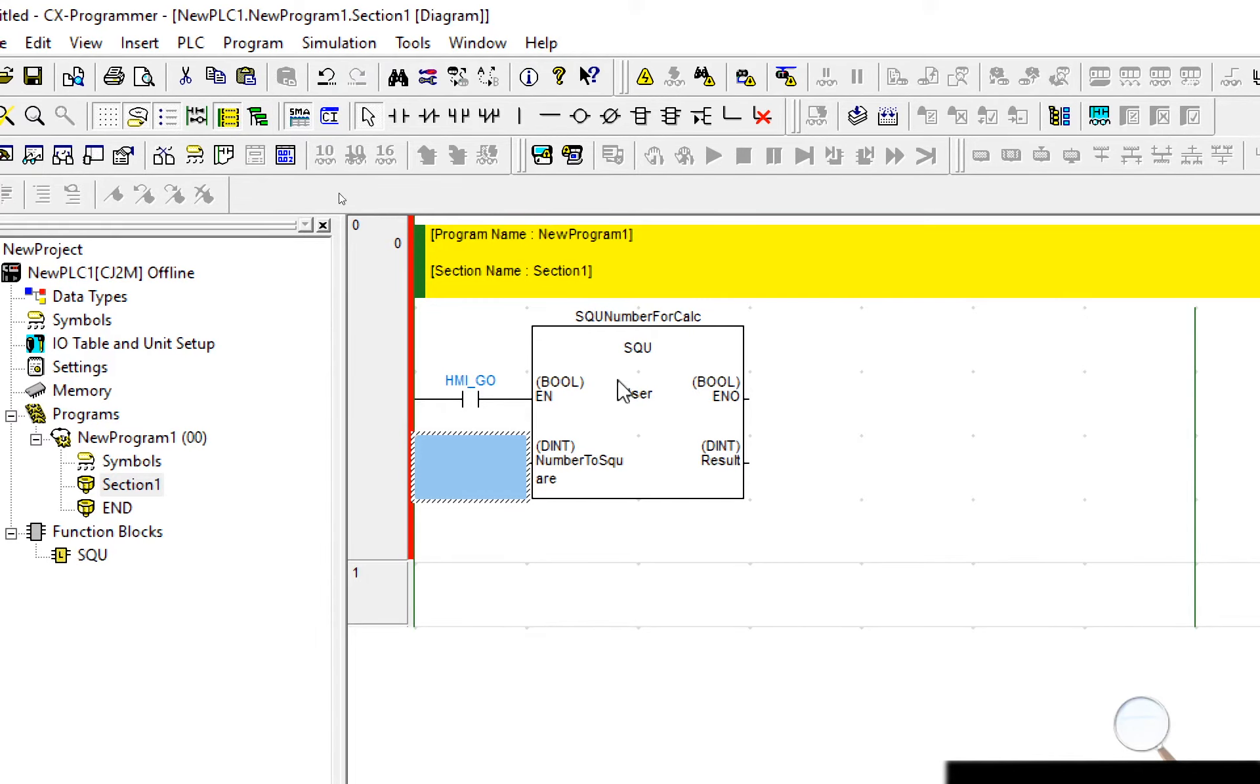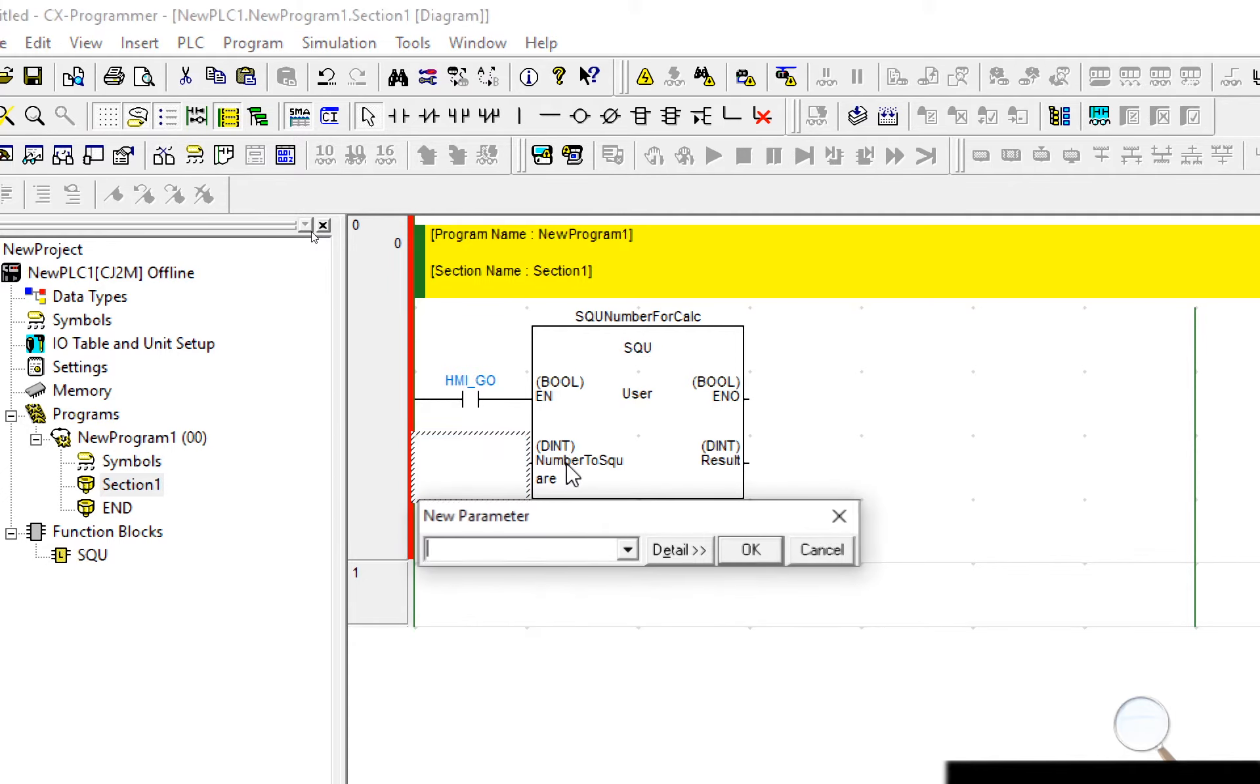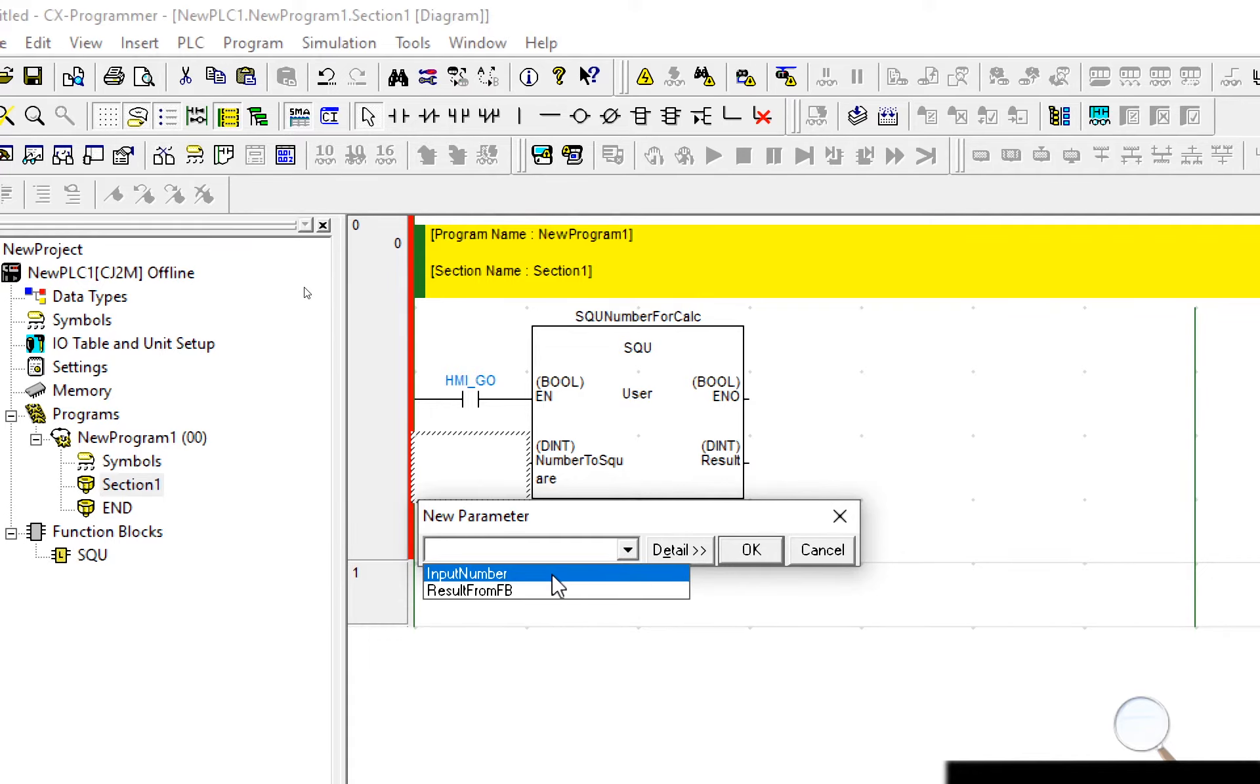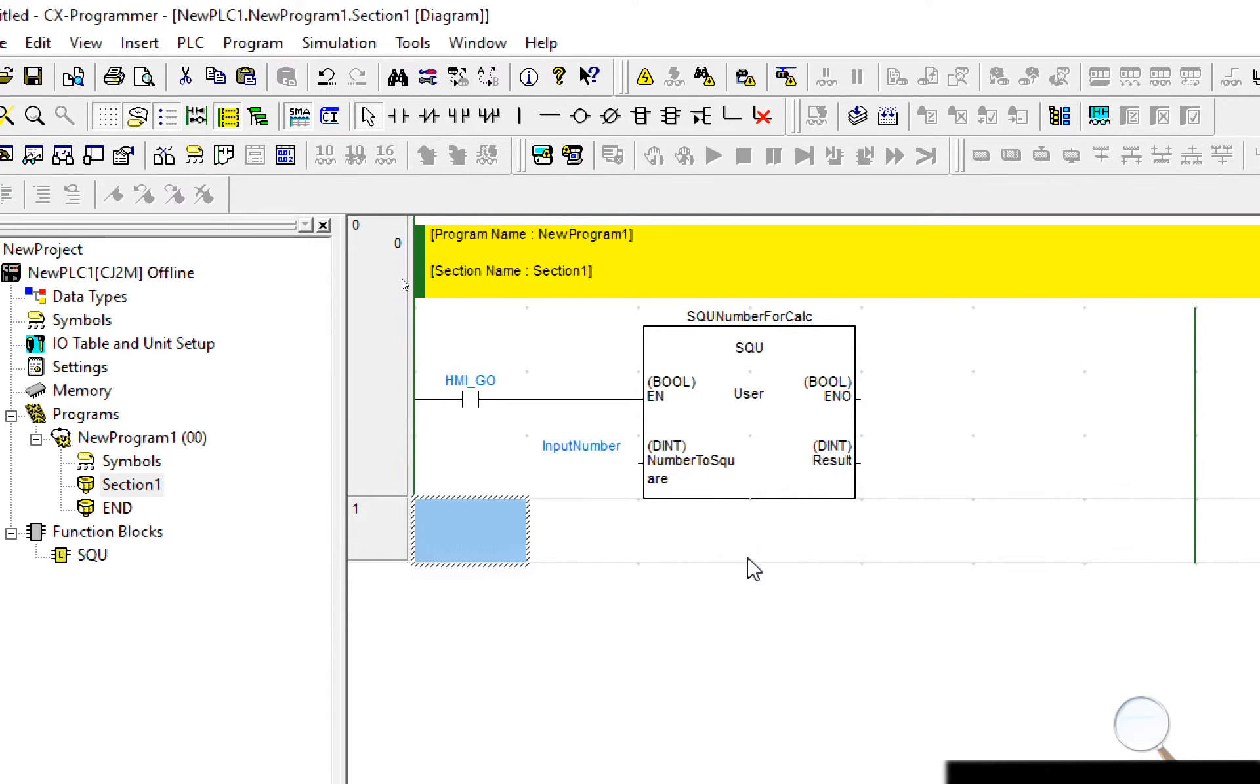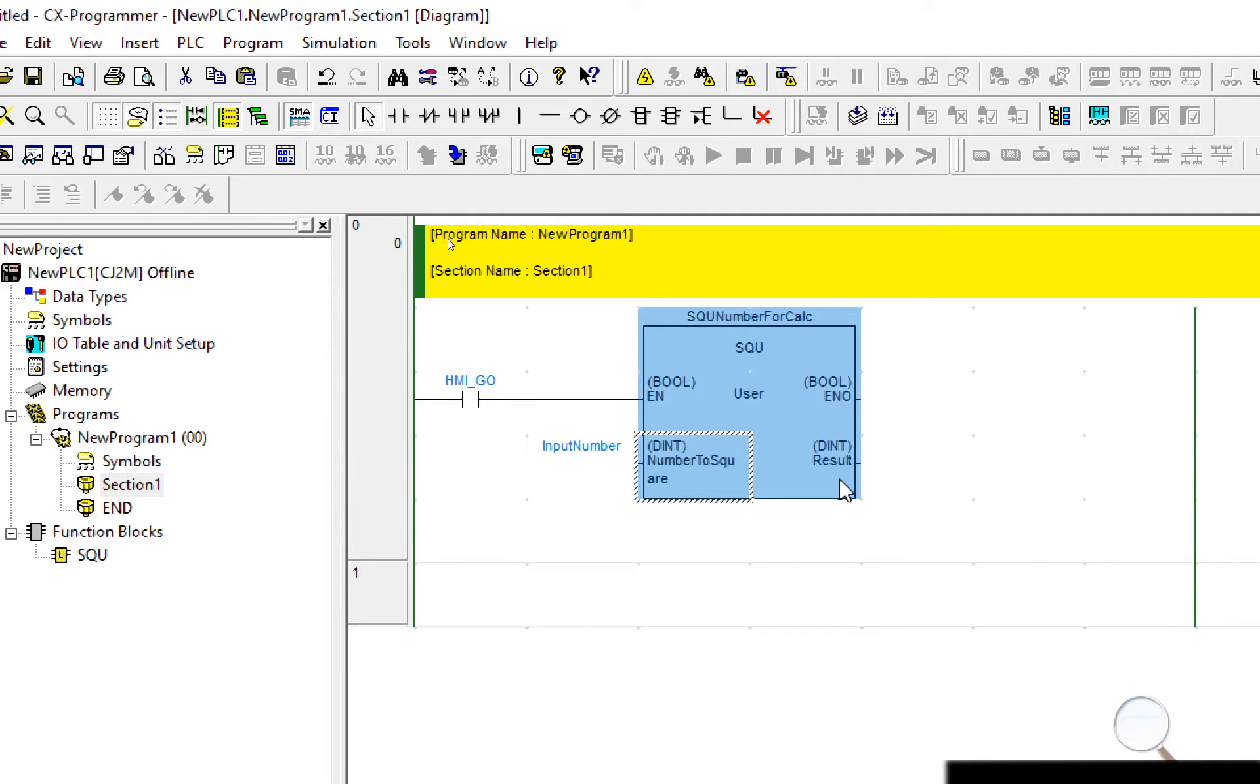The correct method is to select the input or output within the function block, use the arrow keys to move to the left or right and select enter. You are then asked to insert a new parameter. So from the drop down list I'm going to select input number.